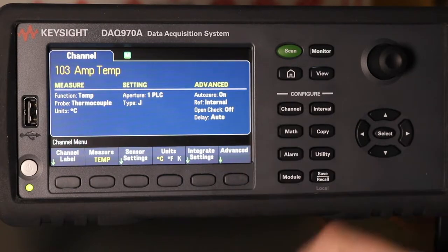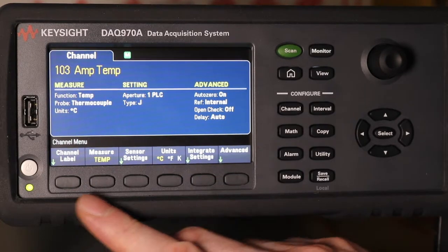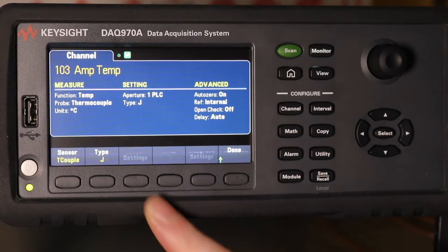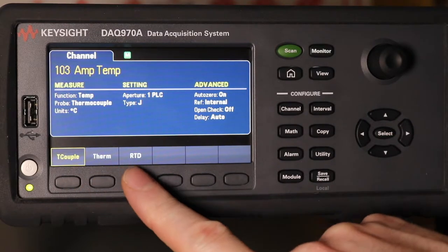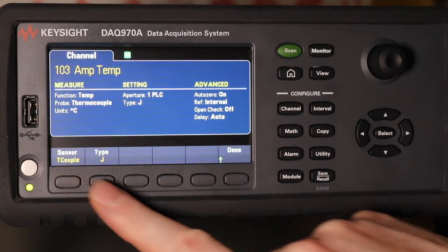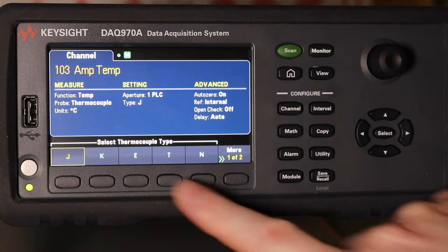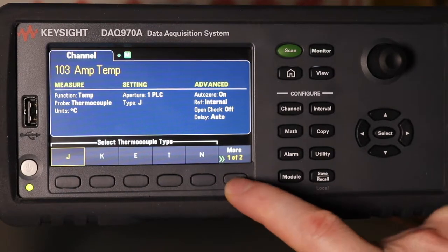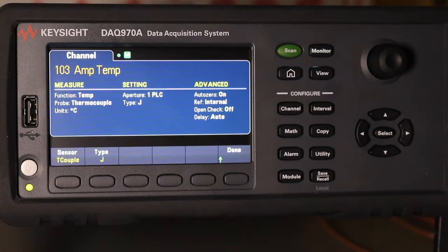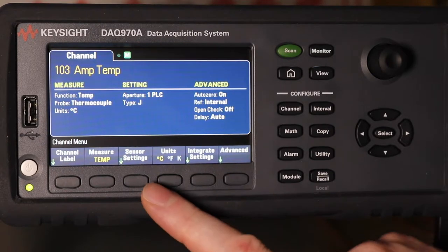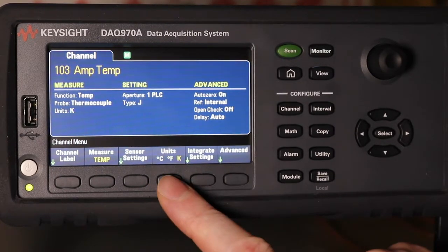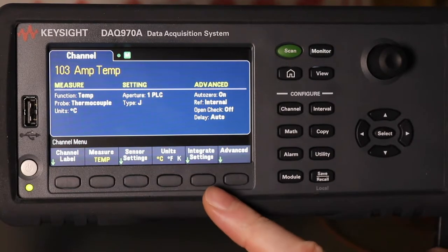Whenever you select temp it defaults to type J thermocouple. But you can change it from thermocouple to thermistor or RTD, and for thermocouple you can get the different types selected. It stays on J by default, and that's it for the sensor settings. You can change the units if you want — I'll leave mine as degrees C.